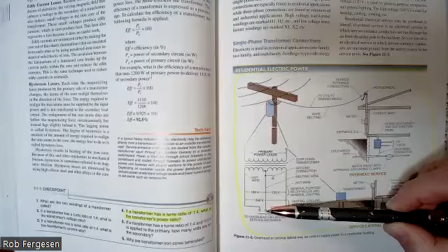They do a center tap, which we'll get into later, in the middle of that transformer, and then they tie that center tap to ground. This is where they drive that giant copper rod down into the ground next to your building. That copper rod is tied to the center tap, so that center tap becomes not only the ground for your box, but also your common wire. In your circuit box, that same wire is hooked up both to your green or bare copper ground wires, and also to all of your white common wires in your single phase system. Some people don't realize that.